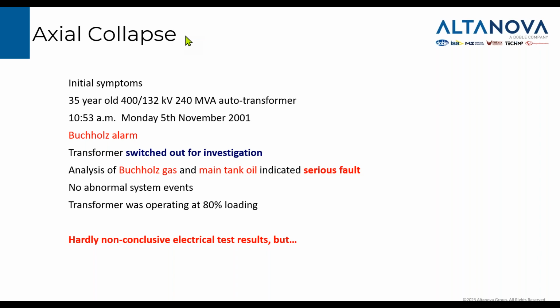Another example is axial collapse of the winding. We had a 400 kV, 240 MV auto transformer located in Great Britain. It was 35 years old, and it presented a Buchholz alarm in 2001. The transformer was switched out for investigation.